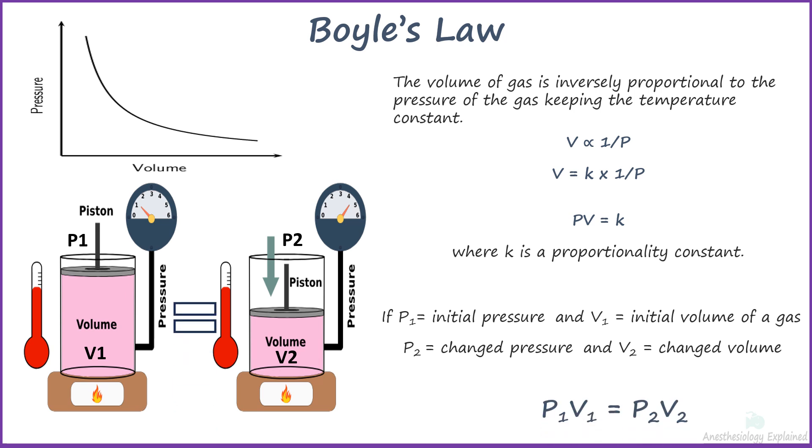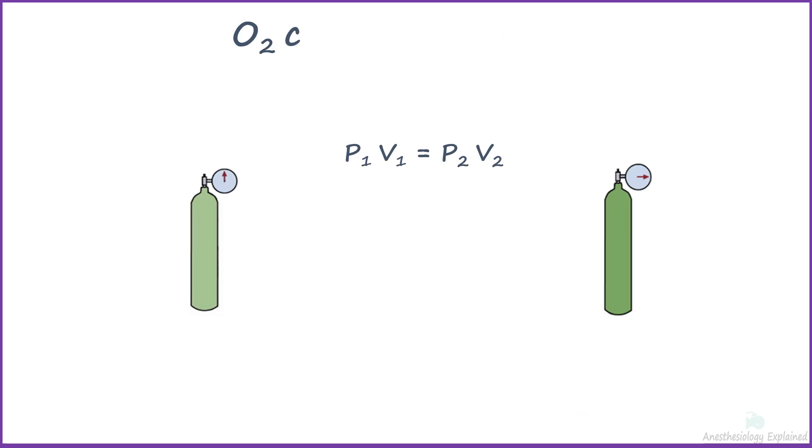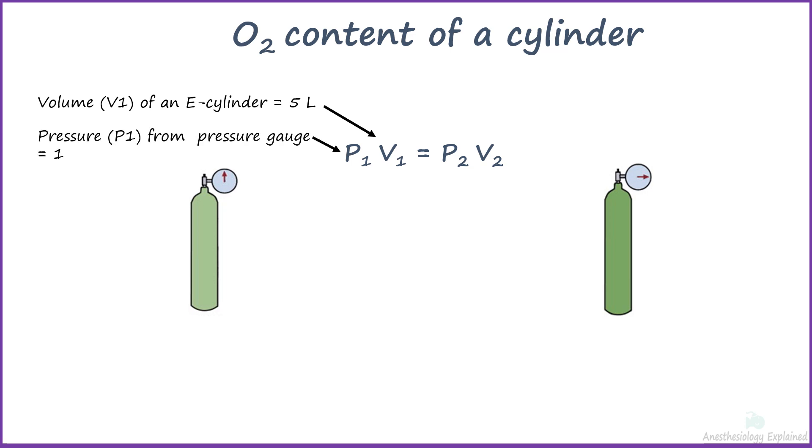This relationship is very useful to determine the volume of any gas at any given pressure in the cylinder. We can apply Boyle's law to measure the cylinder content based on the pressure gauge reading. A typical E-type cylinder has an internal volume of 5 liters. This is the volume V1 of an E-cylinder. The reading on the pressure gauge gives us P1 for that volume, let's say 1500 psi since the cylinder is being used.